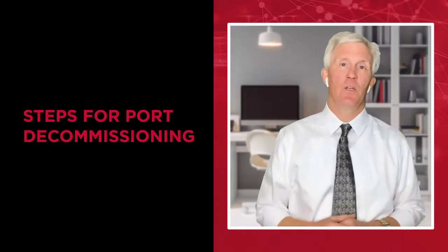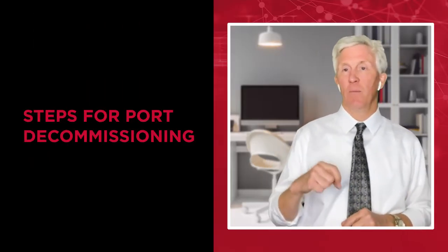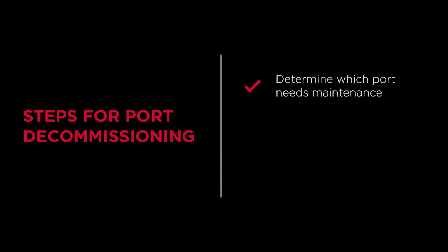Let's say we have an SFP that we've noticed is starting to fade. That is, we can see that the power levels on that SFP have been dwindling over time. And we know that any time that SFP will finally fade to the point where it needs to be physically replaced. So what we want to do is schedule a time to do that maintenance. Since coordinating the activities between a whole bunch of users and applications is very difficult, it's much easier to do this with port decommissioning.